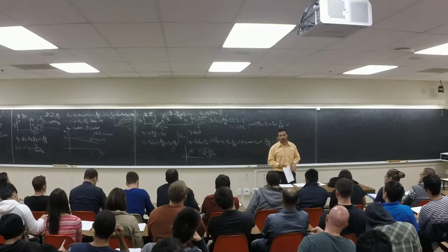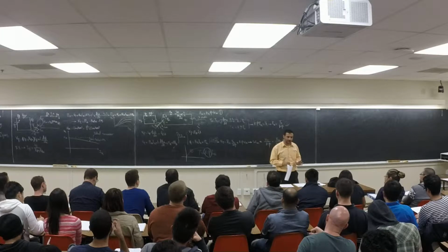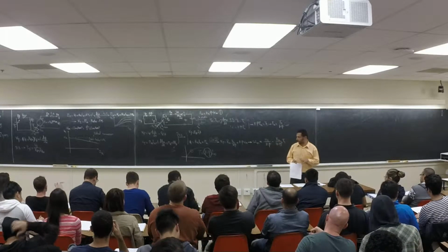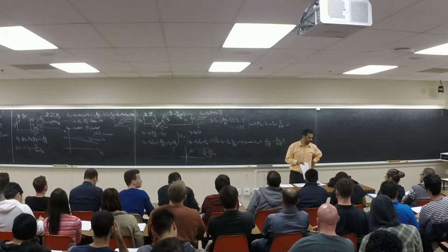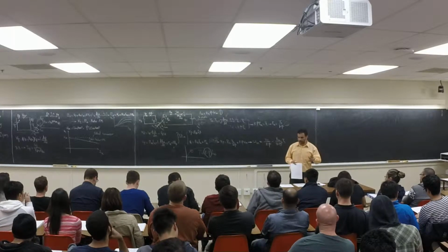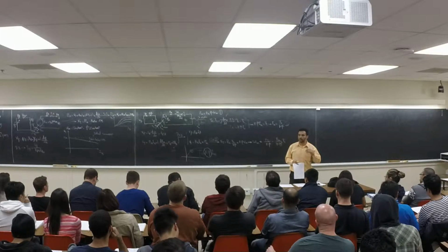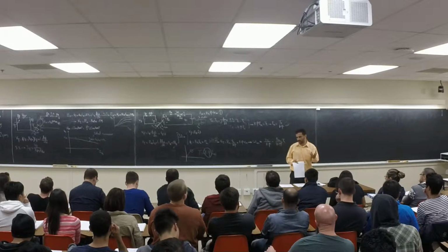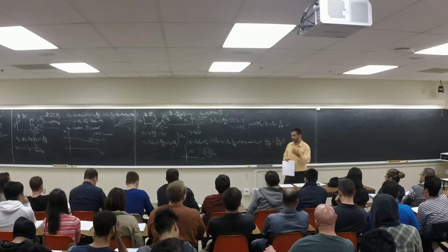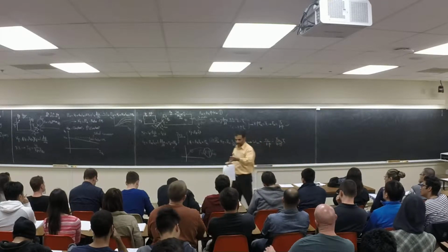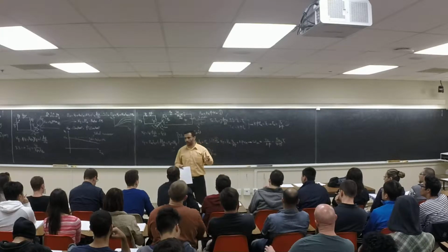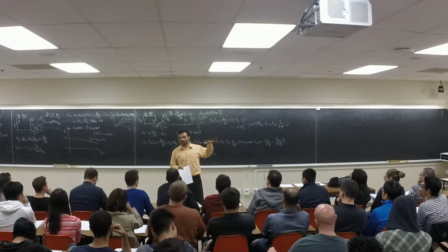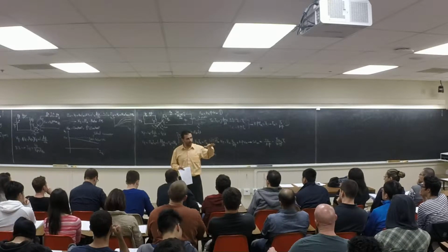You know, we don't do flux control that much unless we get to the field weakening. We have to do that one. I'm not going to talk about field weakening, it would be more like motor drive and those kind of things. But flux control is used, but over the base. For example, they say this machine, the nominal speed or rated speed for this machine is 1000 RPM. If you are going to go more than that, for example, you want to control the machine at 1200 RPM, 1300 RPM, you start to use the flux. You call it flux weakening. You start to weaken the flux.